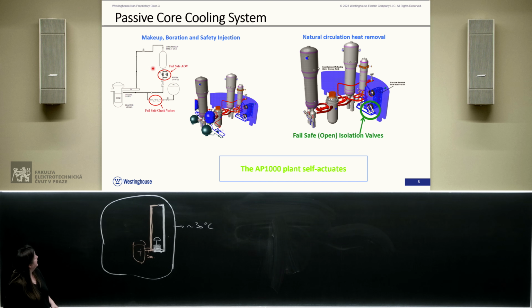The top of the tank is connected by a balance line to the primary system, to one of the cold legs, and it is firmly insulated. I know the name can fool you, but the cold leg is still at 300 degrees during normal operation. It's just colder than the hot leg. So this pipe is going to remain very hot during normal operation. The tank itself and its outlet line are not firmly insulated, so they stay cool during normal operation.